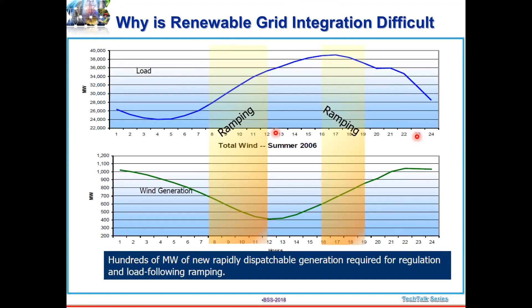These renewables, these solar inverters, don't have any inertia. They will not put any inertia into the system. The fault level will come down. When you bring down the conventional generation, the fault level in the buses will come down. The voltage regulation is directly dependent on the fault level. Higher the fault level, better the voltage regulation. So when you have a reduced fault level in the system because of the backing down of conventional generators, your voltage regulation will be very poor. The voltage will move to the extremes like anything.